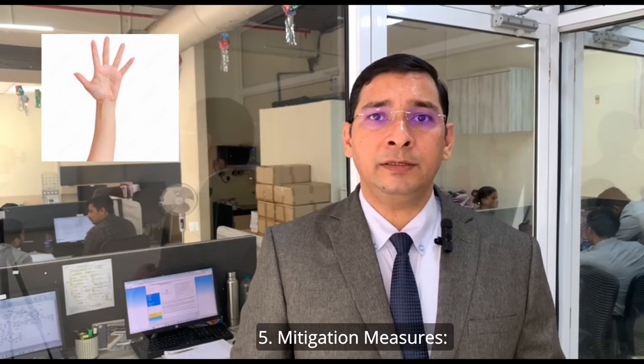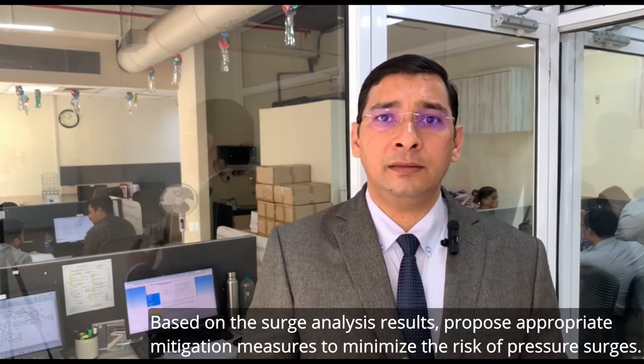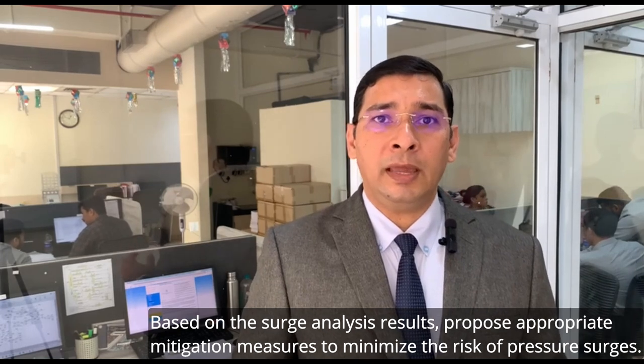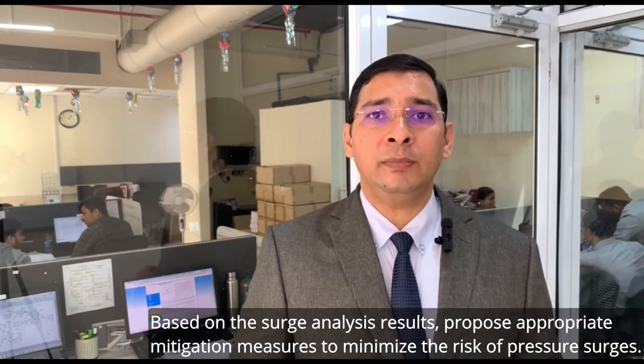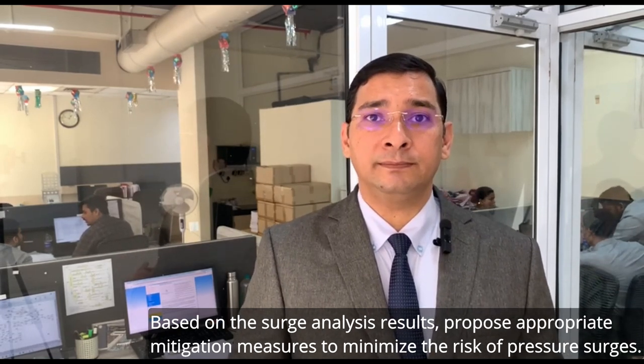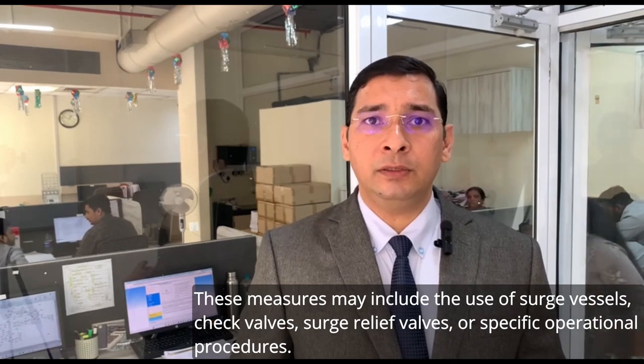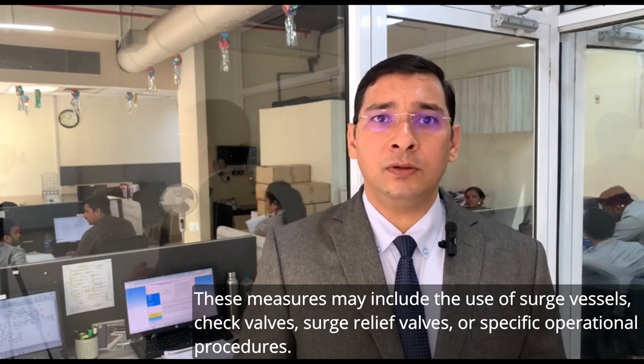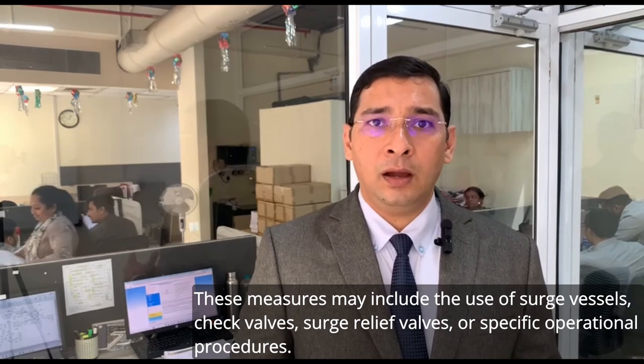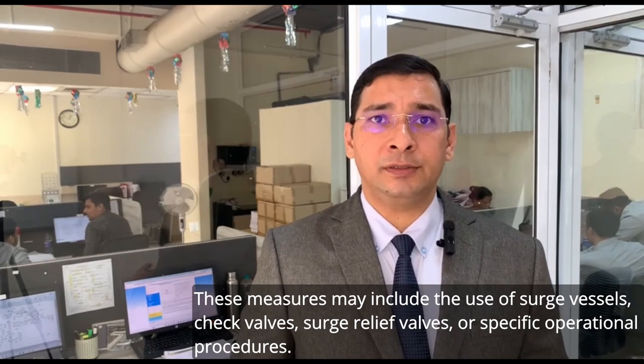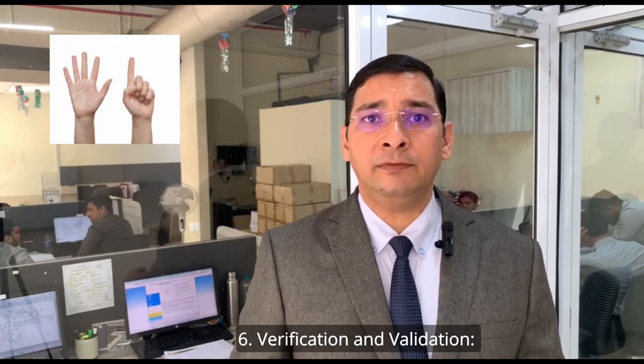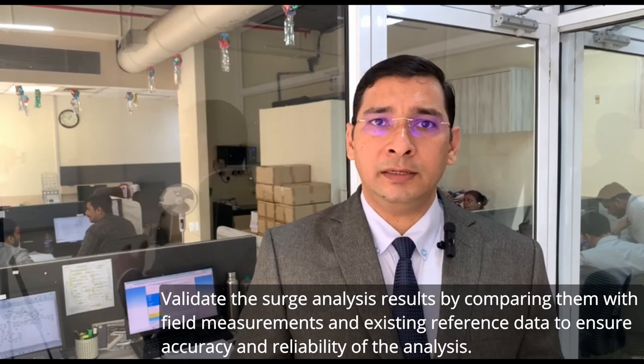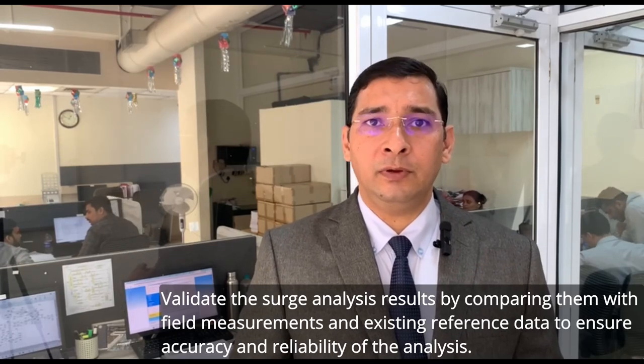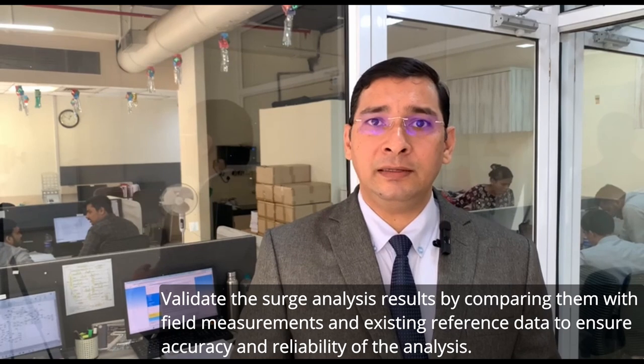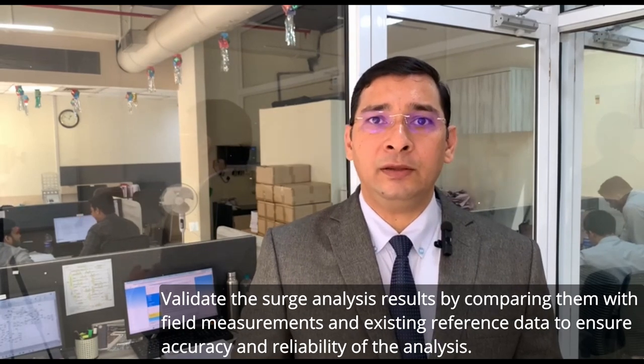Fifth step is the mitigation measures. Based on surge analysis results, propose appropriate mitigation measures to minimize the risk of the pressure surges. These measures may include the use of surge vessels, check valves, surge relief valves, or specific operational procedures. Sixth step is the verification and validation.